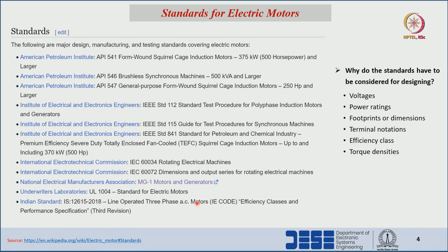The standards for electrical machines — whether motors or generators — must be followed. The key standards are IEEE standards: IEEE 112, 115, and 841 for different electrical machines. IEC standards: IEC 60034 and IEC 60072 are key standards. And NEMA standards — National Electrical Manufacturers Association — MG1 (Motors and Generators) is another standard to design electrical machines.